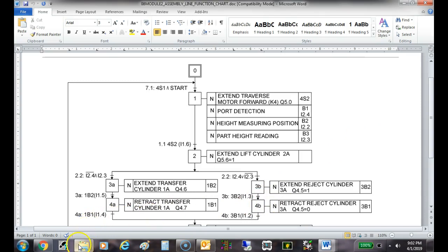So here's the flipper. So it comes up here and stepping motor. So a stepping motor, and we'll look at this a little bit, is a motor that moves in steps. But every step is a precise distance. So what we can do is so many steps on this means move 45 degrees. So right here, when it senses 4B1 and we press the start button, automatically this thing moves 45 degrees, which is where the sensor is for detecting the port, right? Understand that?